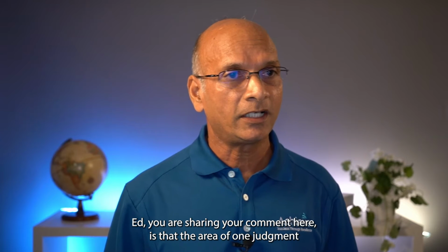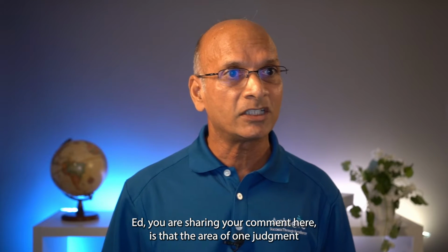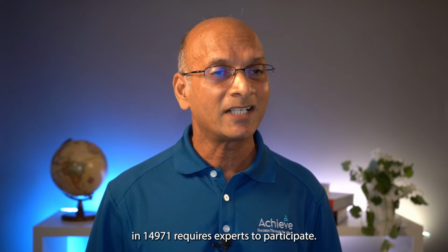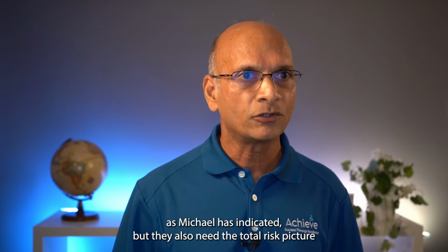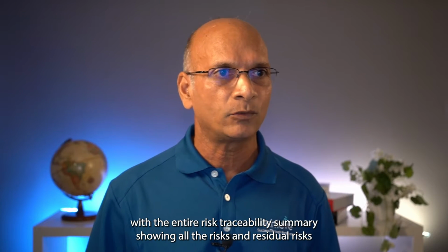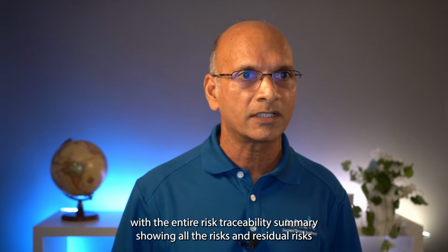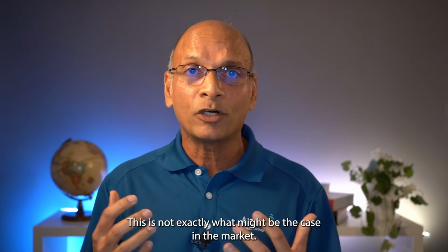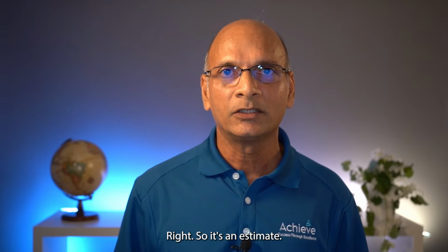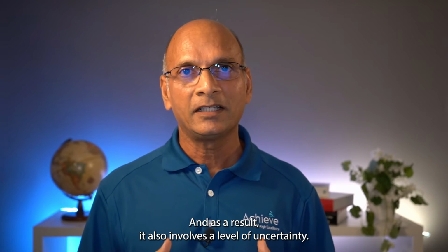Ed, you are sharing your comment that the area of judgment in 14971 requires experts to participate. One of the tools they can use is the visual chart, as Michael has indicated, but they also need the total risk picture with the entire risk traceability summary showing all the risks and residual risks as estimated. So, Ed, you are bringing a point that this is your estimate. This is not exactly what might be the case in the market, right? So it's an estimate, and as a result, it also involves a level of uncertainty.